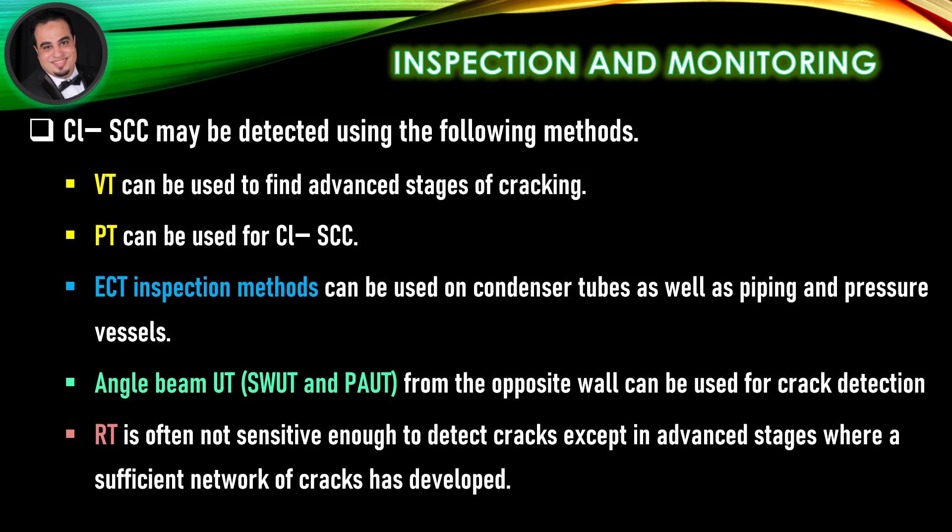Chloride stress corrosion cracking may be detected using the following methods: VT can be used to find advanced stages of cracking. PT can be used for chloride stress corrosion cracking. ECT inspection methods can be used on condenser tubes as well as piping and pressure vessels. Angle beam UT, SWUT, and PAUT from the opposite wall can be used for crack detection. RT is often not sensitive enough to detect cracks except in advanced stages where a sufficient network of cracks has developed.